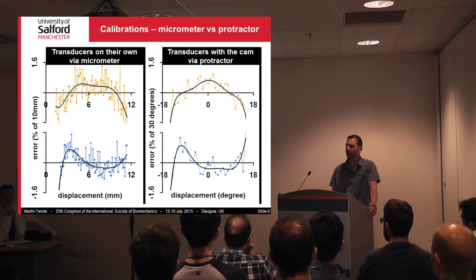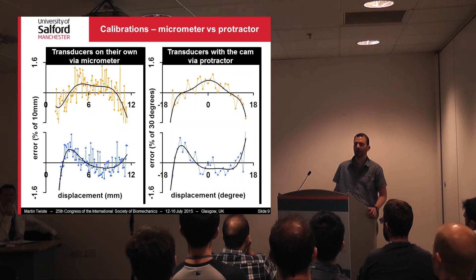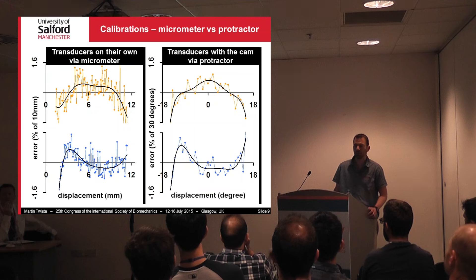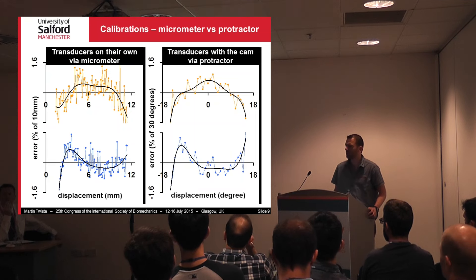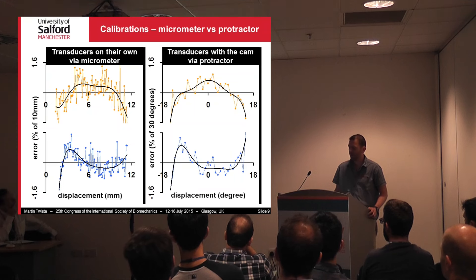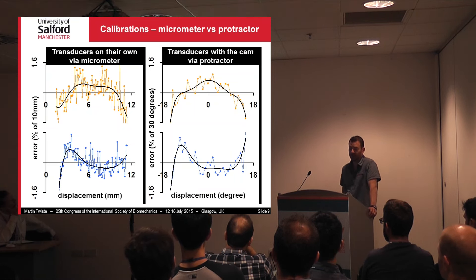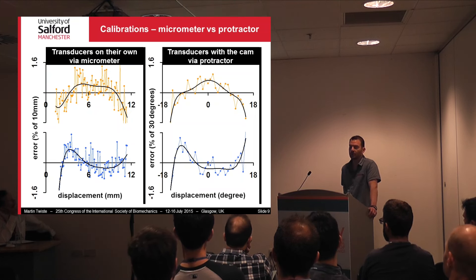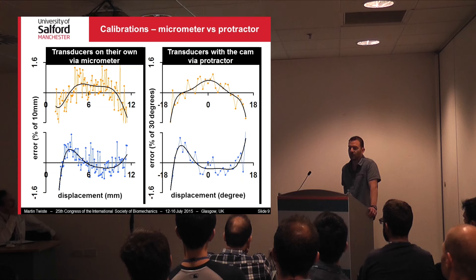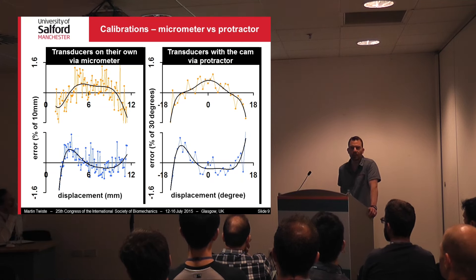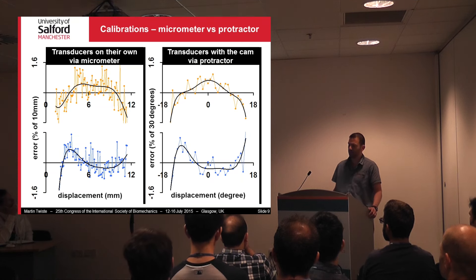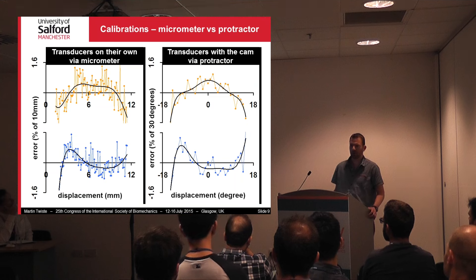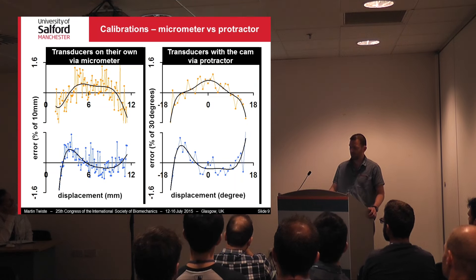Here we can see the comparison between micrometer calibration on the left and protractor calibration on the right. The top row shows transducer one, the bottom row transducer two. We fitted a sixth-order polynomial to the data, represented by the black line. As you can see, the black line on the left for both transducers is very similar to the black line on the right. The error inherent within the transducer itself was repeated within the cam, meaning the cam very accurately captured the motion.